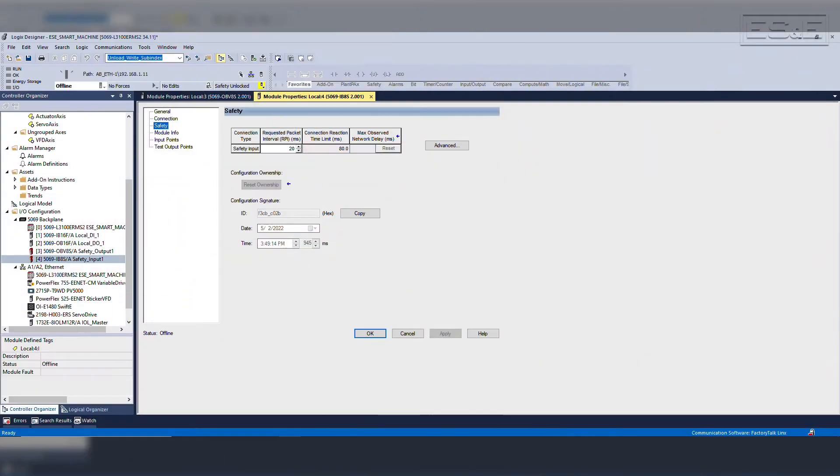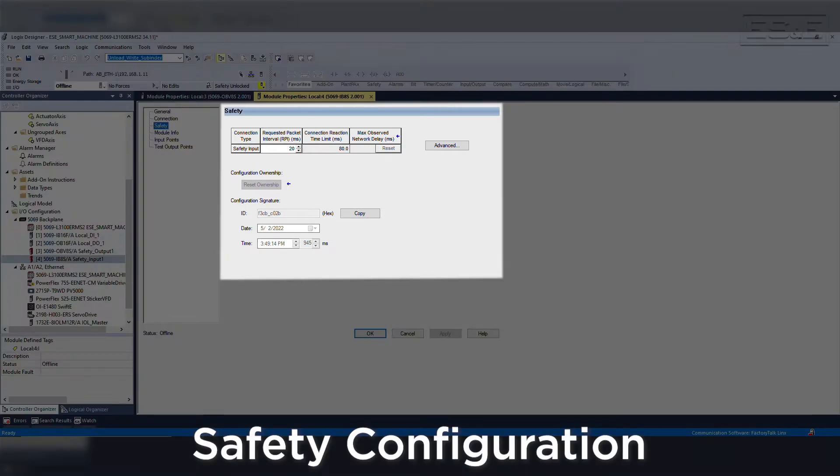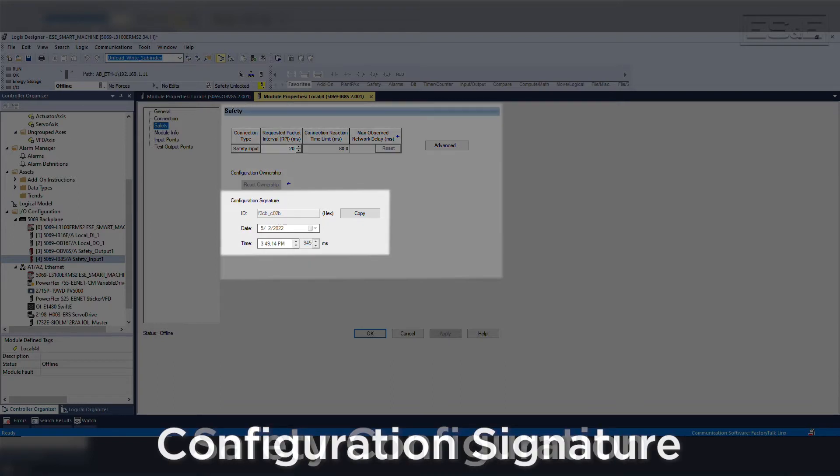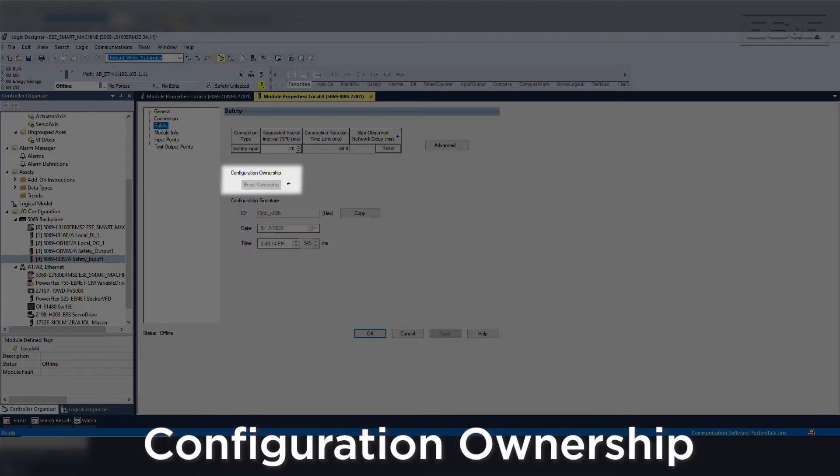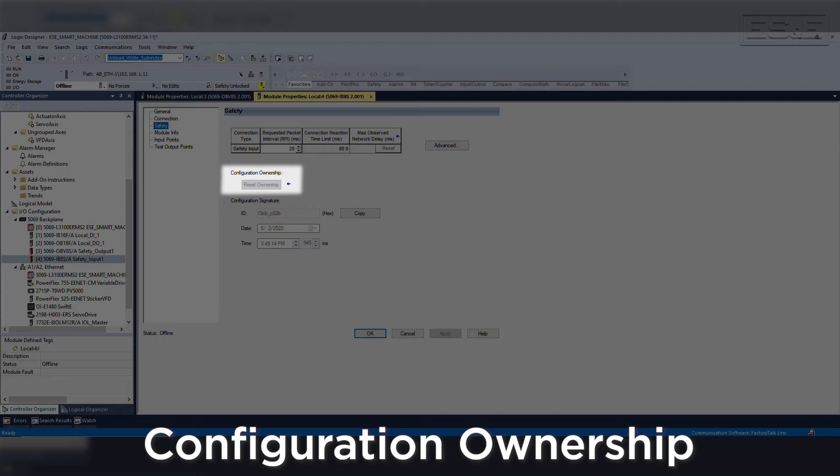When adding I/O modules to the controller project, there are a few additional configuration requirements to ensure the safety network and safety signature are set up correctly. Each module will have its own unique configuration signature that is based on the specific hardware. Also, within the safety tab on the module configuration, you will need to ensure the proper controller has ownership of the module. This allows the controller to verify the safety configuration when adding the safety signature and validating the safety system.